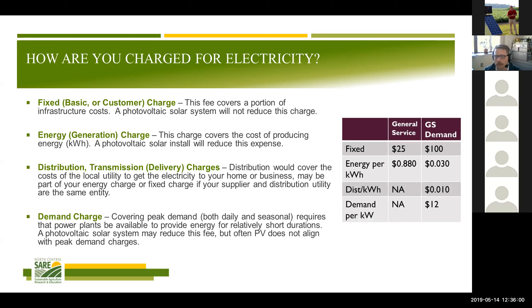The energy charge is whatever you're charged per kilowatt-hour, and it usually includes the value of the fuel — the coal it took to run a coal-fired power plant, or the natural gas for a gas plant. Distribution and transmission charges cover getting that electricity to the customer, and sometimes energy and distribution are combined into one charge. Then finally there's demand, which is a fee based on your peak use at a given moment in time.